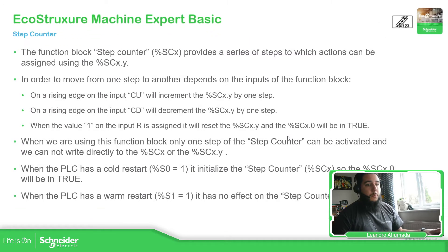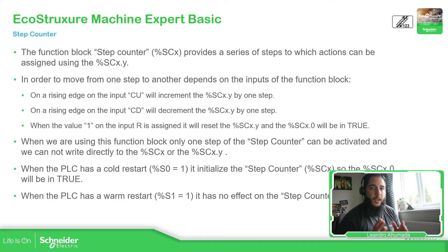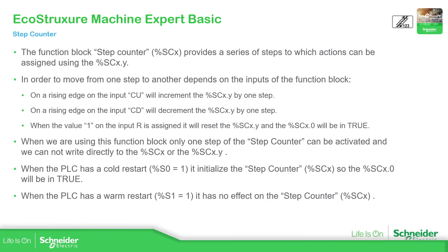In this part you can see that the step counter starts with the %SC and then we have the instance of this variable. What's different is that the steps that we have are assigned to this percentage variable that we have used. This function block has some inputs: ones regarding to the counter up, counter down, and then we have one to reset the actual value of the step counter.